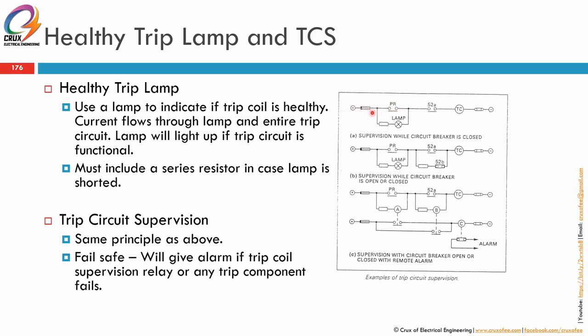So the current will flow through this lamp. If you can see here, this is actually a small resistor. So this current limiting resistor is to limit the current just enough to light up the lamp, but not enough for it to energize the coil of the trip coil. Okay.